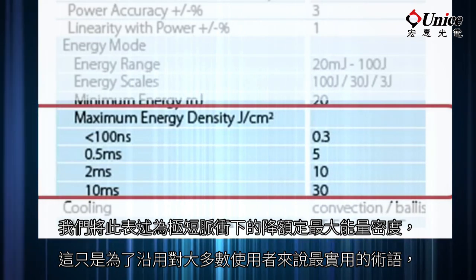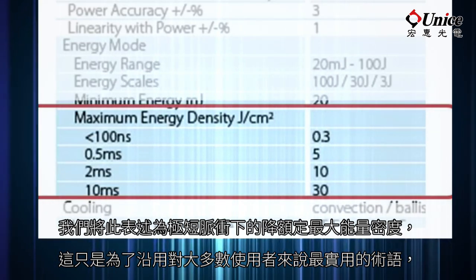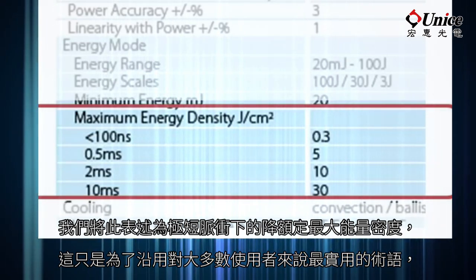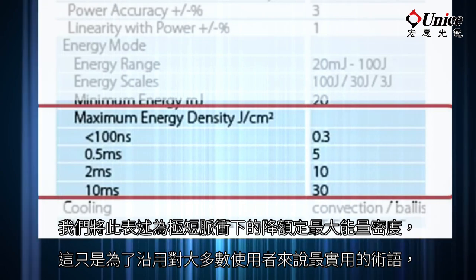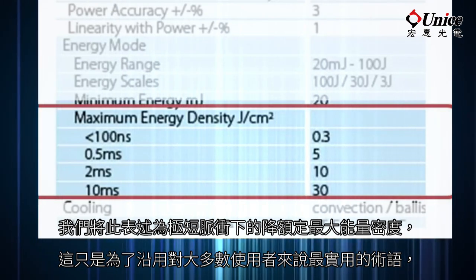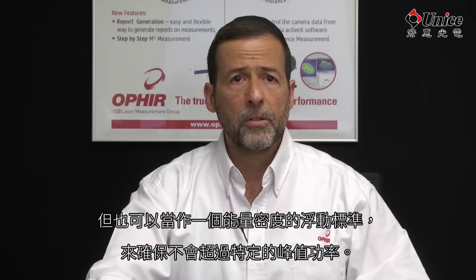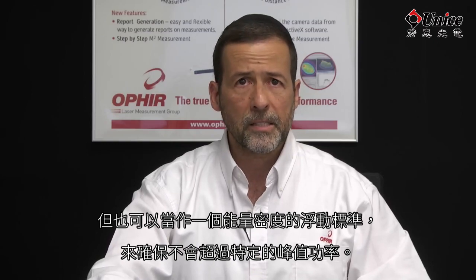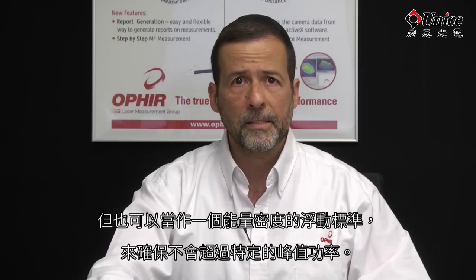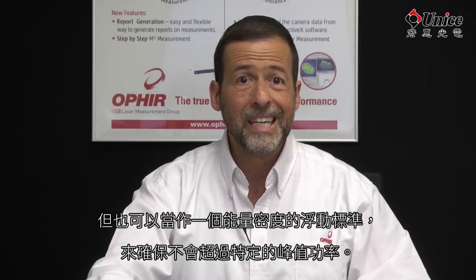We frame this as a derated maximum energy density for very short pulses, simply to stick to terminology that's most practically useful to most users. But one could just as easily look at it as a sliding scale of energy densities to ensure that a given peak power is not exceeded.